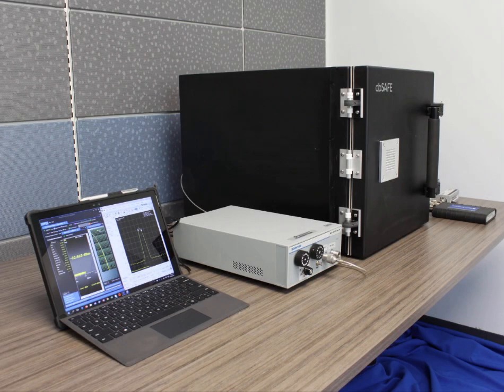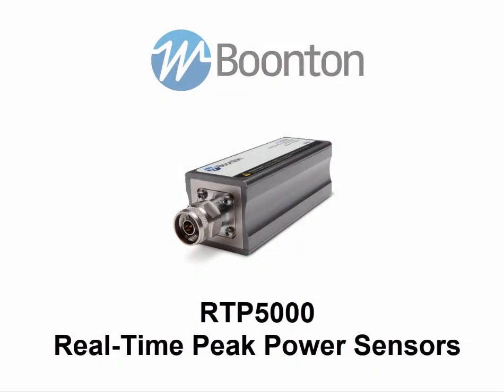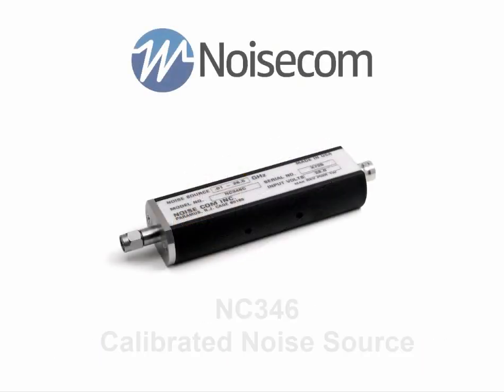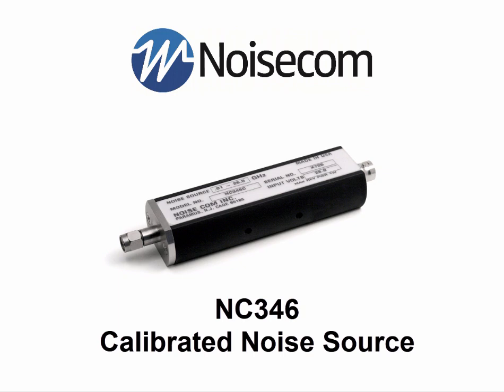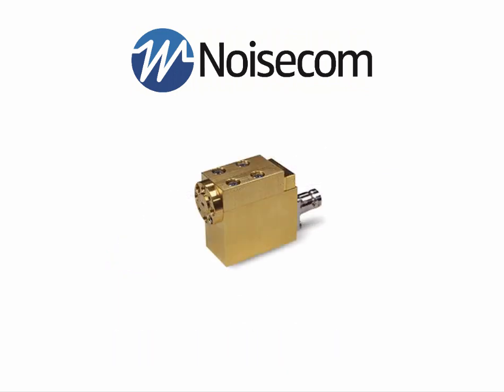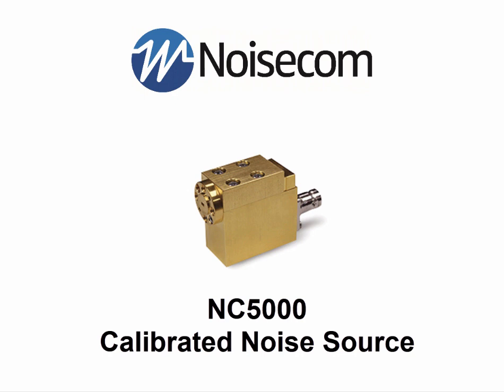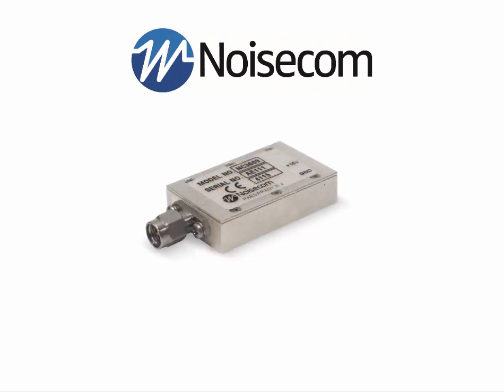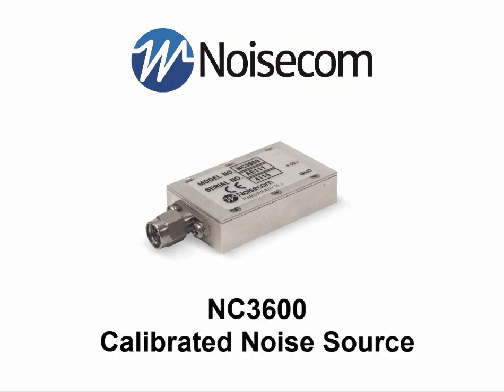The demonstration today is going to highlight how we use Boonton Electronics peak power sensors, the RTP5006, and Noisecom noise sources for over-the-air measurements. Noisecom has been providing noise sources from 700 MHz to 110 GHz, which is ideal for today's evolving 5G and mmWave development of MIMO chipsets.